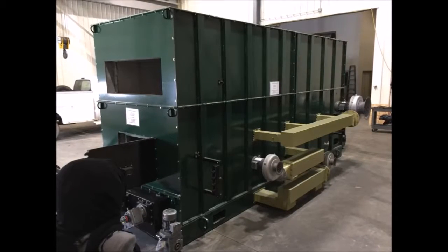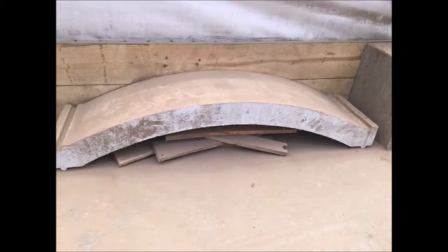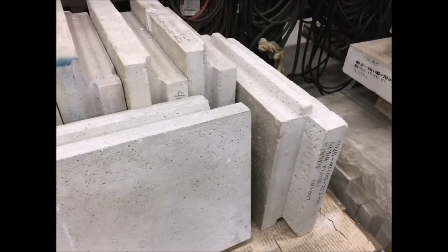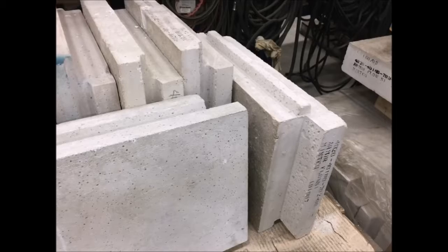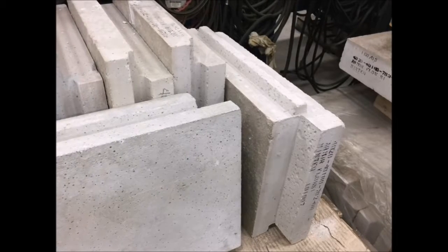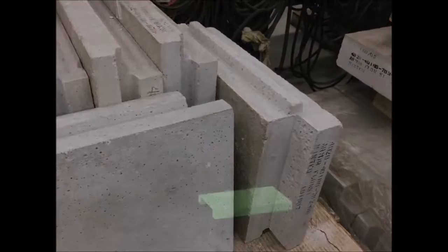The combustor is essentially two large chambers, each lined with refractory blocks, such as these curved roof blocks and these straight wall and floor blocks, shaped with tongue and groove joins to avoid using mortar that would crack with heat. This effectively insulates the chamber against heat loss, which in turn maintains efficiency. Let's build a system of our own to see how it all fits together.